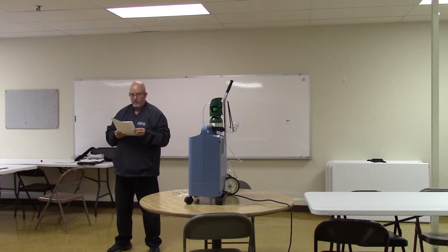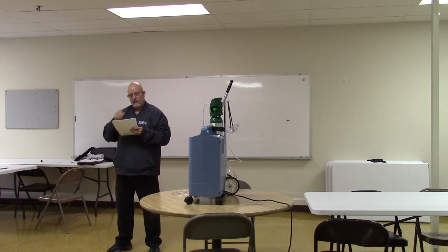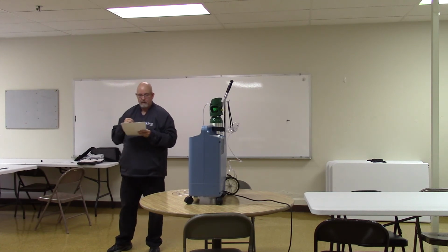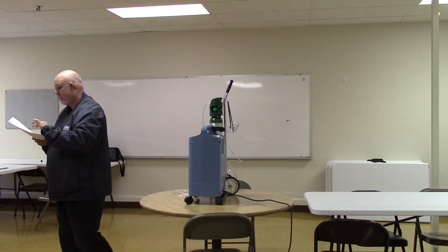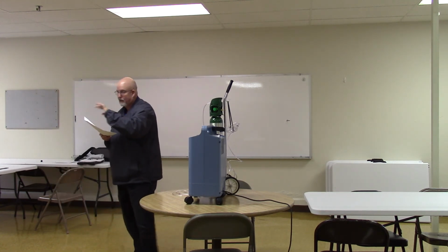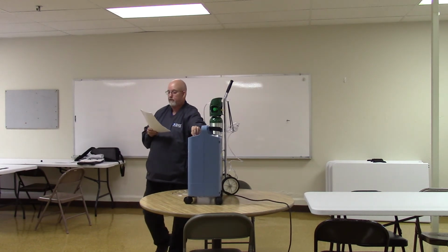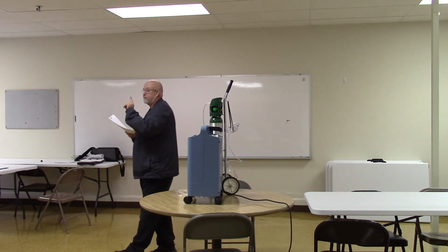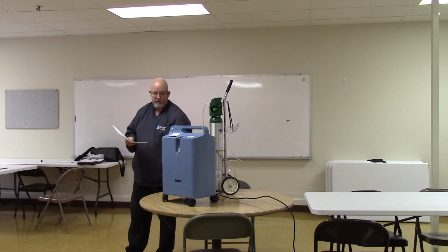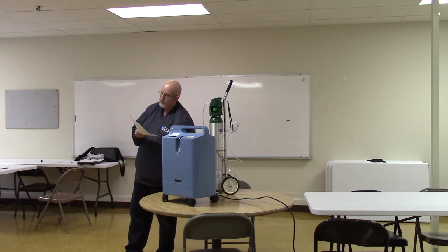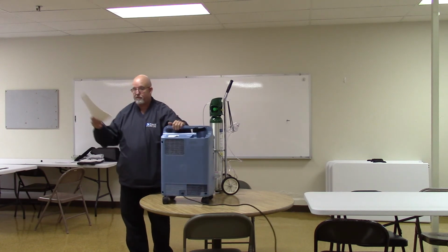You should clean your concentrator filters yearly. All right, now, I did say that. But what they're talking about here, I think, is the cabinet filter, which I told you you don't have, right? This one, you're right, is yearly, so that's kind of a trick question. But weekly for your cabinet filters. If you've seen concentrators with the black filters on the sides, those need to be cleaned weekly, and I think that's what this test is actually talking about.